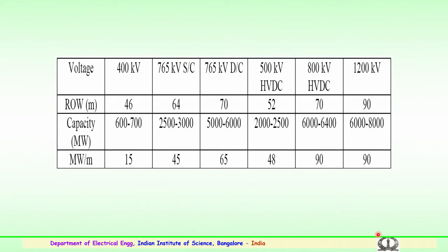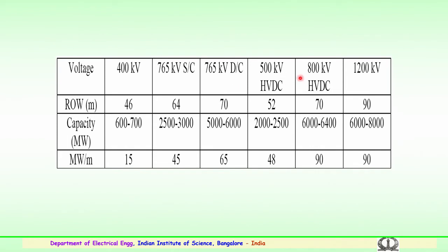A comparison of voltage levels and right of way: 400 kV requires a minimum of 46 meters; 765 kV single circuit requires 64 meters; 765 kV double circuit requires 70 meters; 500 kV HVDC requires 52 meters; 800 kV HVDC is 70 meters — not much different from 765 kV double circuit; and 1200 kV HVAC requires 90 meters minimum right of way.